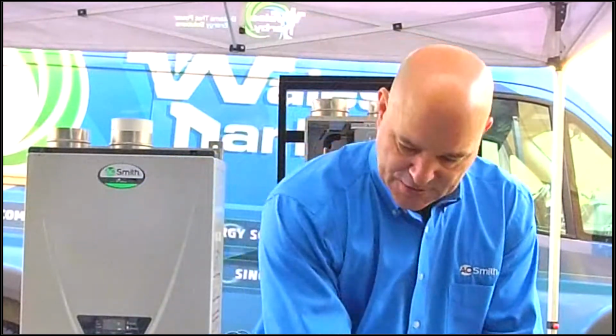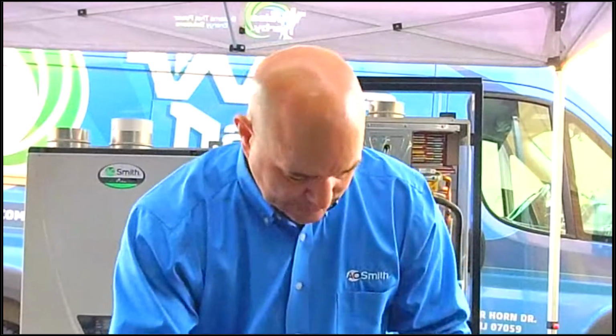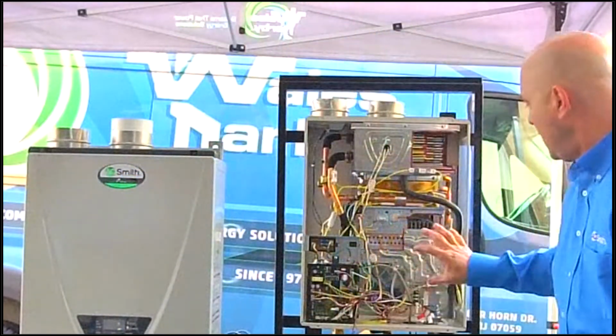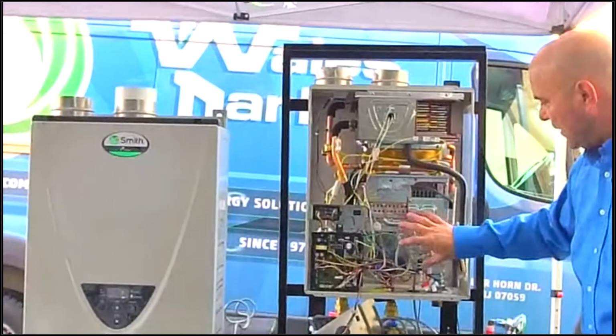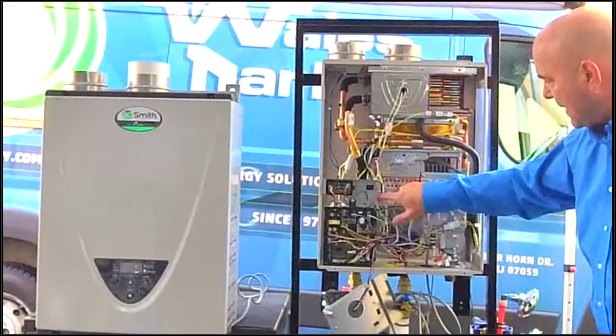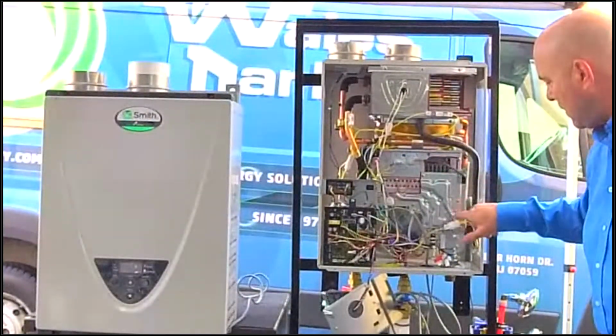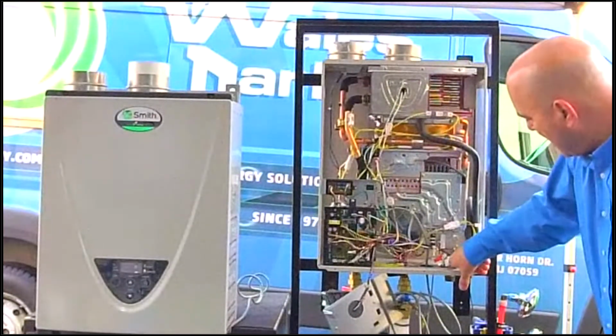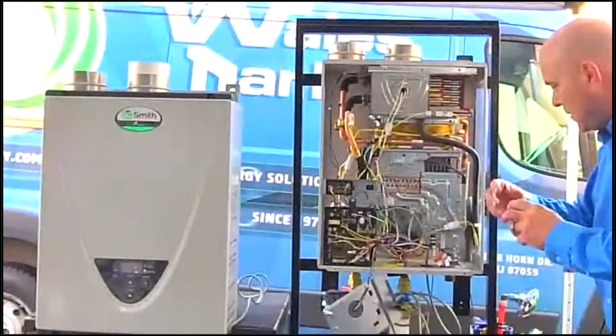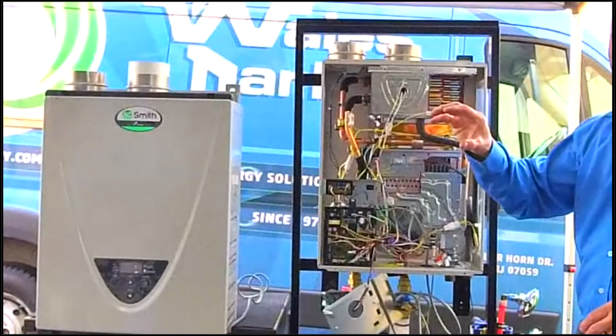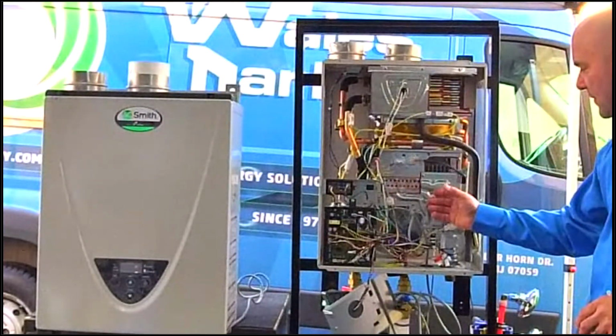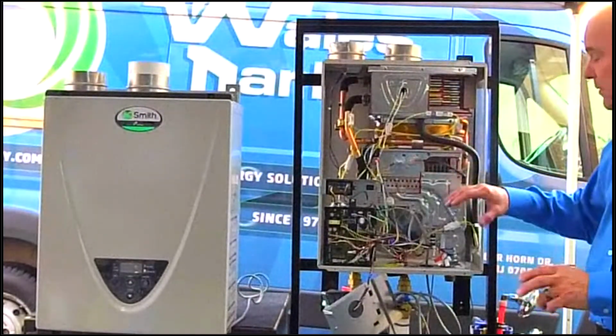I just always make sure that's in there, because we would put combusted air into the space. So, the gas train here: if this ever had to be replaced, it's about 8 screws right along here, and then there's one down the bottom. You take your solenoid wires off, this will lift right out, and it's replaceable. You don't have to tear the whole unit apart to do that.